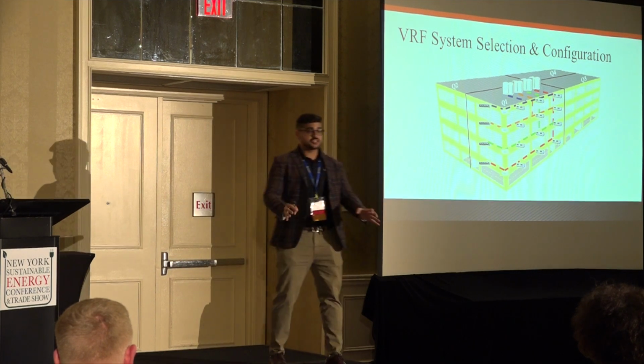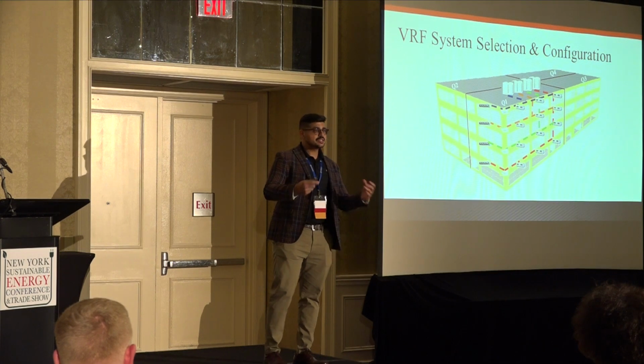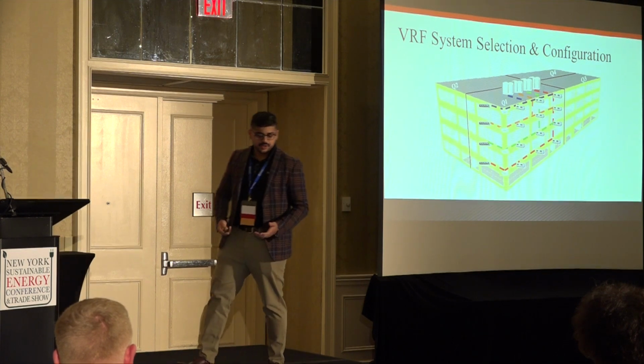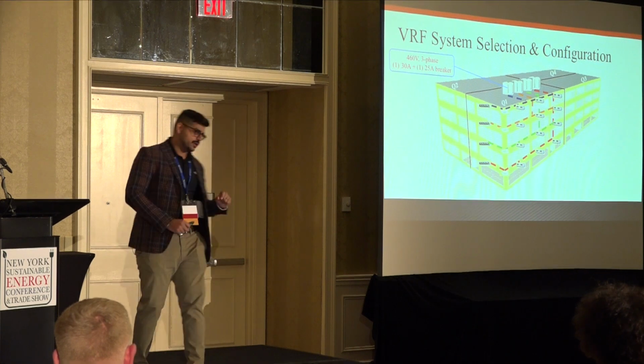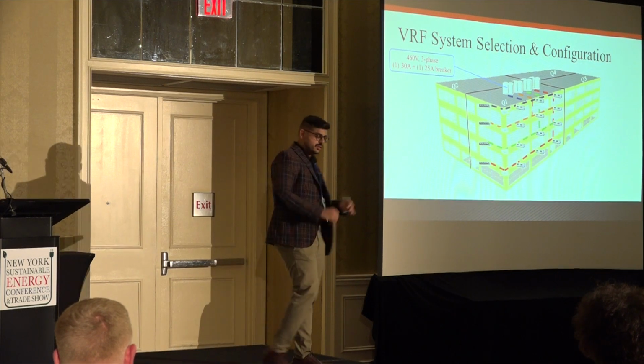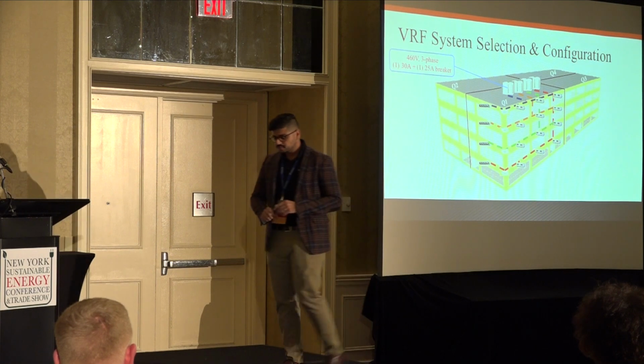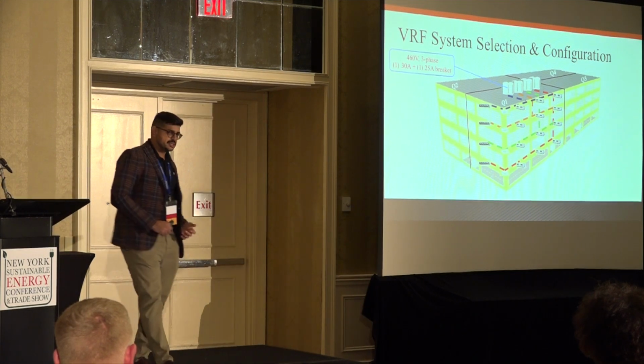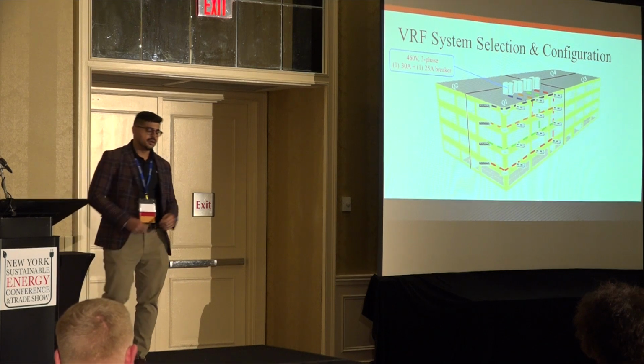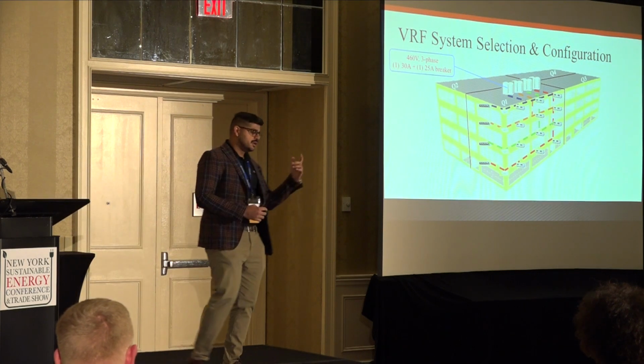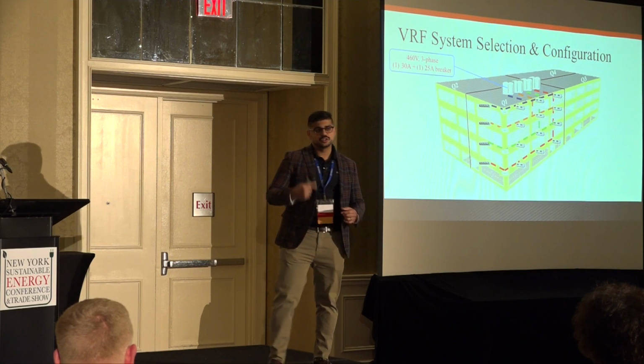Okay. All right, so this is how the system looks like, again, on paper. What does it look like to an end user who's in this building, right? So, well, actually, before that, let me go into the electrical. Okay, so there is 460-volt power in this building, 3-phase. So the outdoor units that are selected are 460-volt, 3-phase power. It's a bank of 2 outdoor units in a system, so they need one 30-amp breaker and one 25-amp breaker. Okay, the indoor units in a system, all of them can be powered by one 15-amp breaker. So together, in one system, you need a 70-amp breaker size, right?